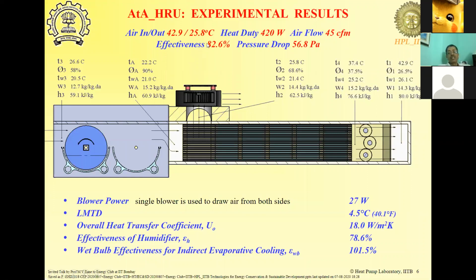Coming to the exhaust heat recovery system. Now, if we are talking about a place like Mumbai, where your relative humidity is very high, what do you do there? In that case, we may not be in a position to reduce the temperature to such a low value unless the moisture is removed. So removing the moisture can be done using liquid desiccants. Now, liquid desiccants are salt solutions which have high affinity for water vapor. It's just like jaggery. You keep jaggery outside in the rainy season in Mumbai, and you'll see that it becomes soggy because it is hygroscopic.